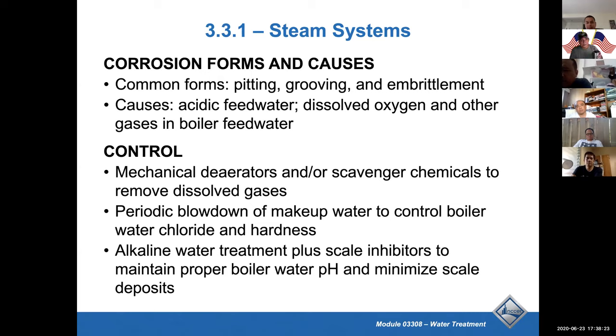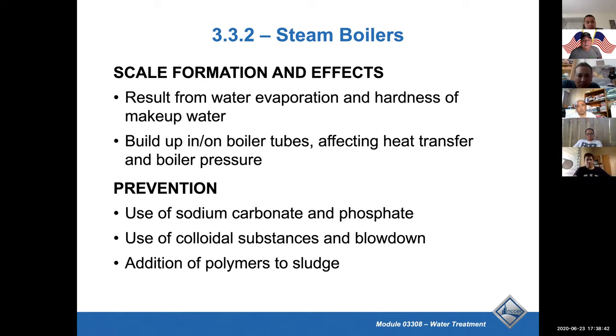Steam systems, they're still talking about steam systems. Pitting, grooving, embrittlement. The causes for corrosion are acidic feed water, dissolved oxygen and other gases. I'm not going to talk a lot about boilers. In boilers, you use a lot of sodium carbonate and phosphates. It's a chemical additive.